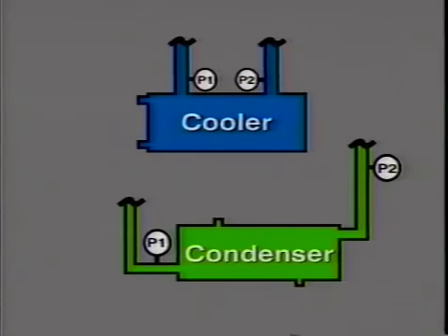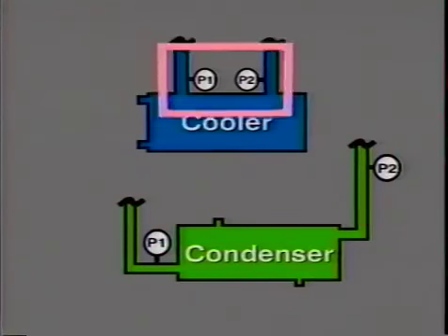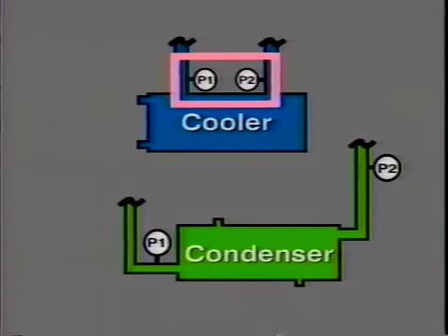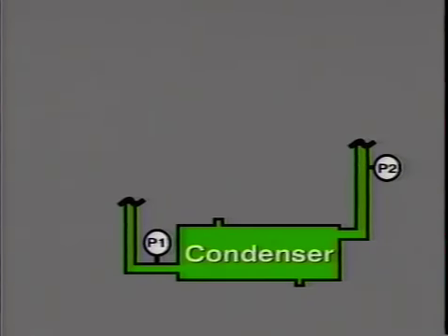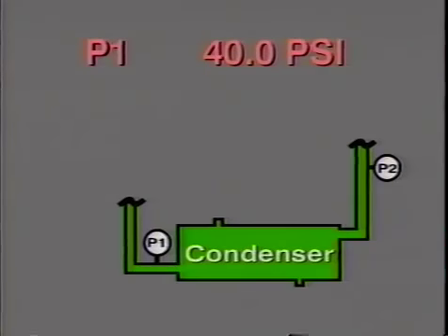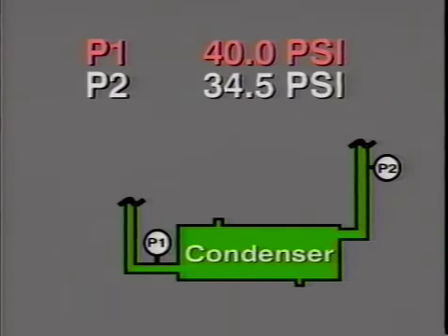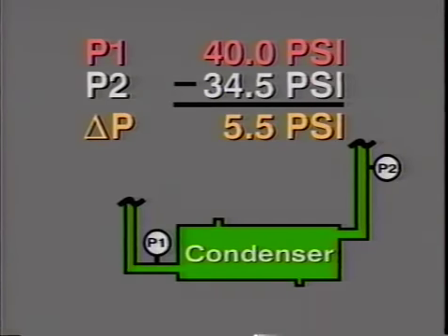Pressure taps for taking pressure readings across a heat exchanger should be as close to the inlet and outlet as possible and at the same height. This may not always be the case, and if there is a difference in the height of the gauges, a correction will have to be made as outlined in the following example. Measure the entering pressure P1, 40 psi. Measure the leaving pressure P2, 34.5 psi. Now determine the pressure difference, delta P, where delta P equals P1 minus P2, or 40 psi minus 34.5 psi, which equals 5.5 psi.